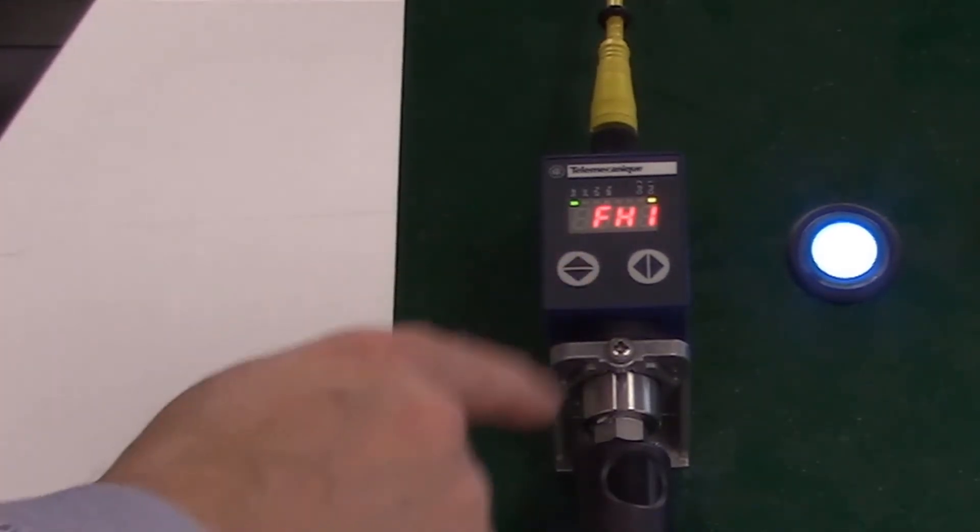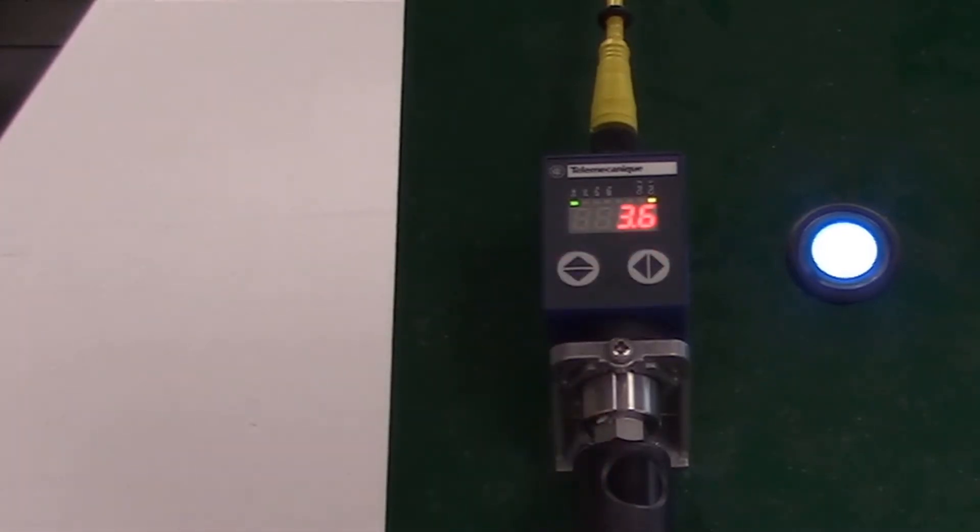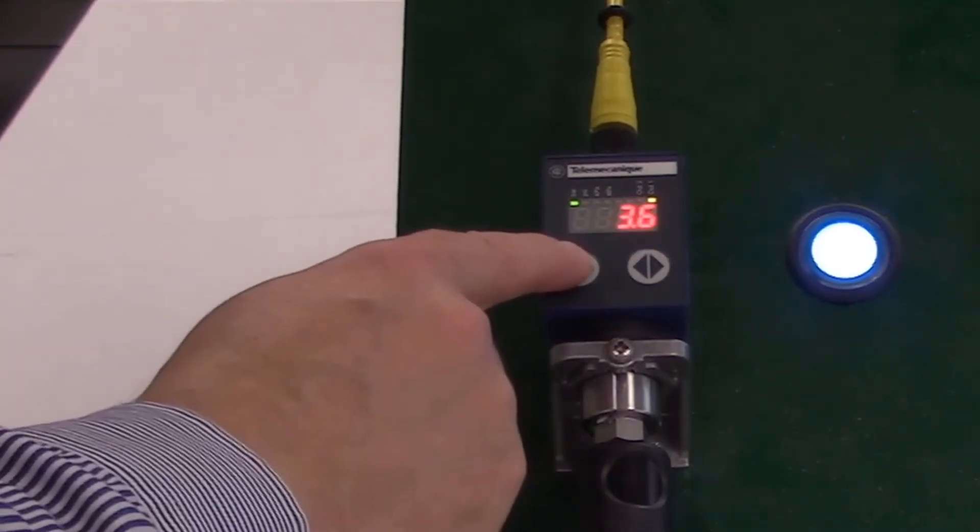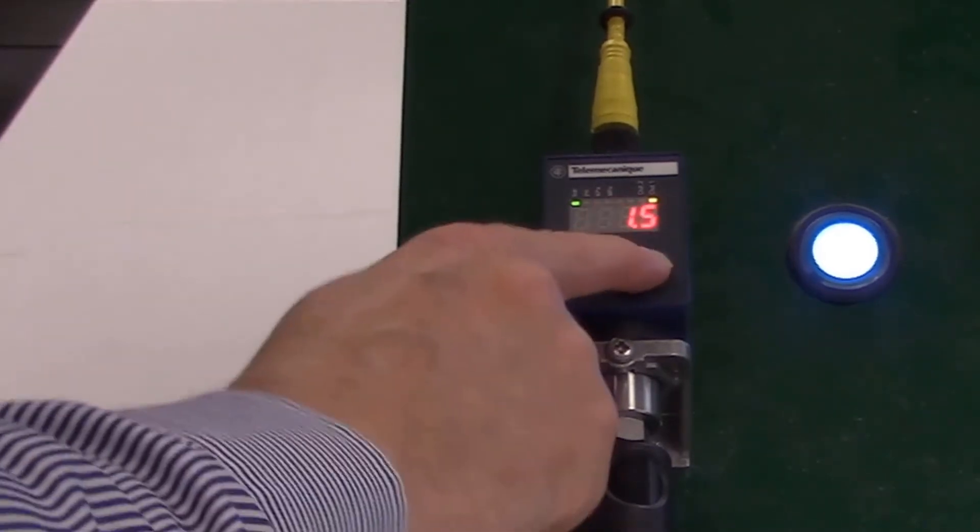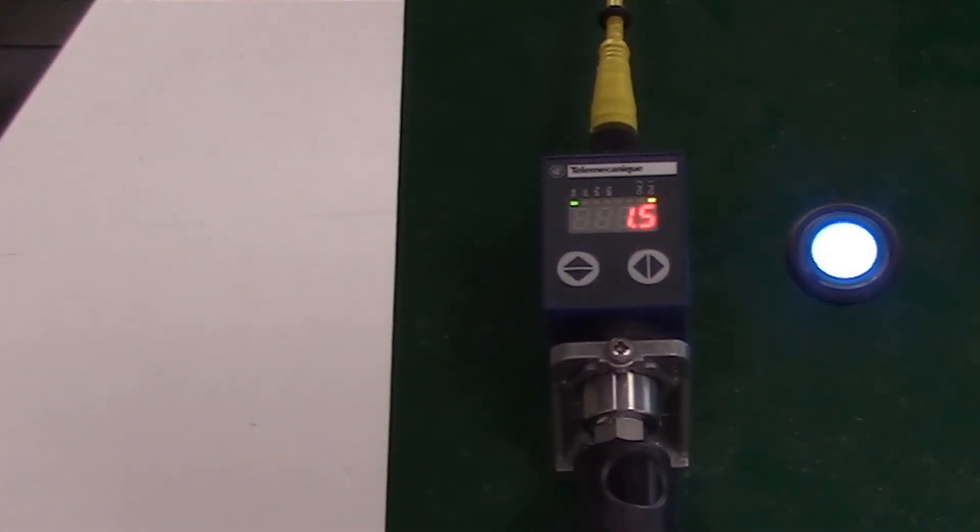The FH1 is set to 3.6 bar, often called the high point. And FL1 is set to 1.5 bar, often called the low point.